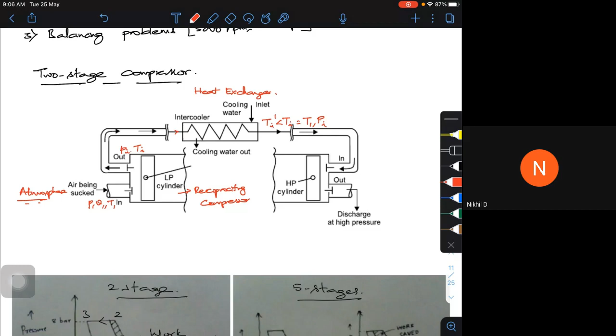If I follow this particular path, this is your high pressure compressor. I'll be able to reach a higher point in T2. I'll be able to compress it to a higher pressure if it is at a lower temperature in the high pressure cylinder. This will be at a lower temperature and higher pressure. So it will enter here and be compressed to a high pressure, which I call P2 and T2. That's a discharge at higher pressure. This is how a two-stage compressor will work.